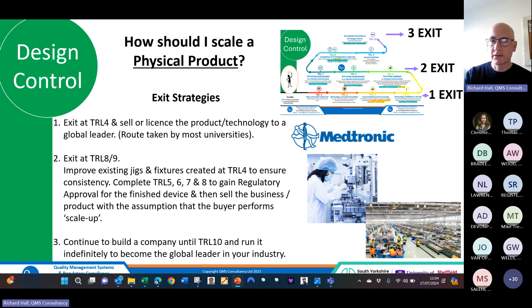With software, it's slightly different. Generally speaking, software exits at TRL 10 in most instances, and that's because the process of getting software to market is a lot less costly because you haven't got a physical product to build. But it's important to think about how you're going to build the software. Software engineers either build the software ad hoc all the way through TRL 3 and 4. They then rebuild the software at TRL 5 and validate their software before completing 6 and 7. Or you can use 62304 to fully validate the software from TRL 3 onwards. And effectively, you can skip 5, 6, and 7 because you'll do the analysis for that in TRL 4.